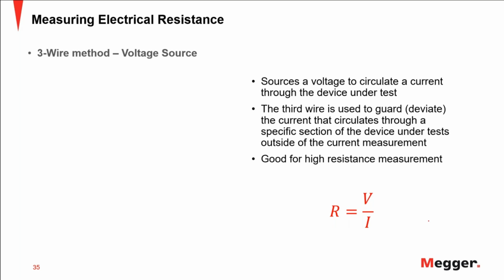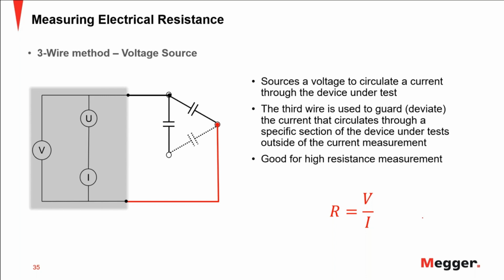So I mentioned the methods, and for the insulation resistance test, there's also the 3-wire method. Here you see that I only have 2 wires: the conductor applying the voltage, and the wire returning the current back to the instrument. Let's say that because of the characteristic of the measurement or the asset that you are testing, you're going to have multiple paths, but you only want to measure the insulation resistance of this section, so this part.